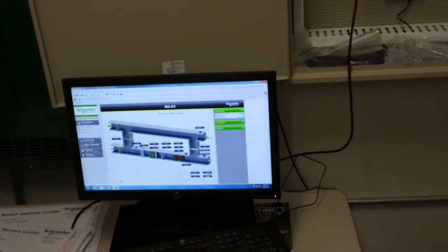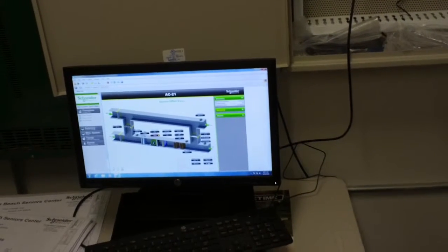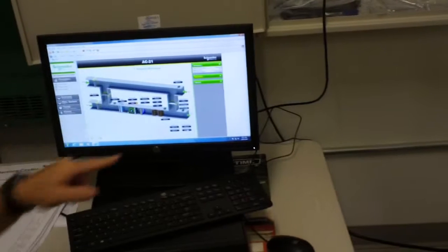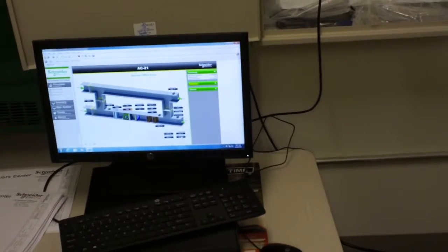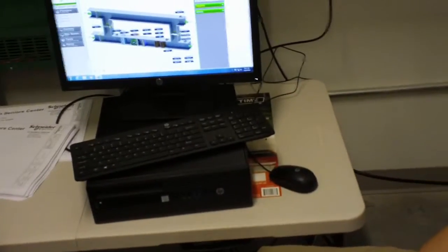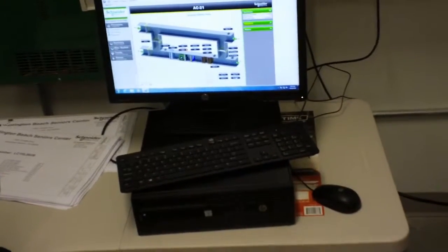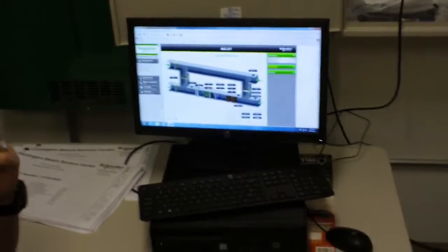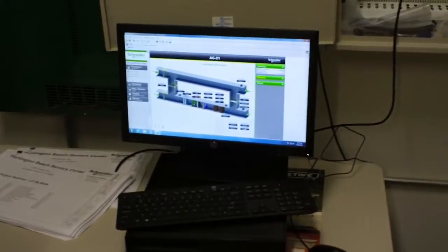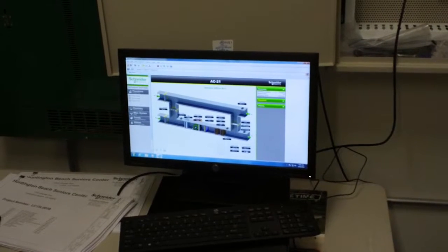There's also the bypass controller. There's temperature sensing. So let's say all of our zones are kind of throttled down. They're all pretty close to satisfied. You're basically just cycling on itself with the bypass sitting at 100%. If the unit is still calling for cool, your supply air temp, I don't know what the cutout is on that, would you happen to know? But basically, if your supply air temp were to get down below 48 degrees, it will actually turn cooling off and use the air inside the system. So it just stays there until it starts cooling again. Once that warms up, it compresses back. Otherwise that will freeze your unit up, and it's controlling the position off the static pressure of our supply air. It should be good. It's a good setup.